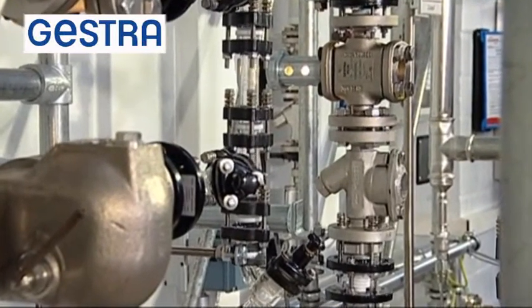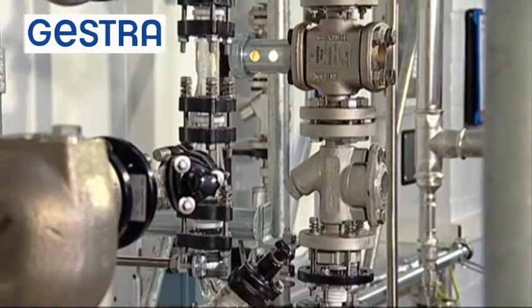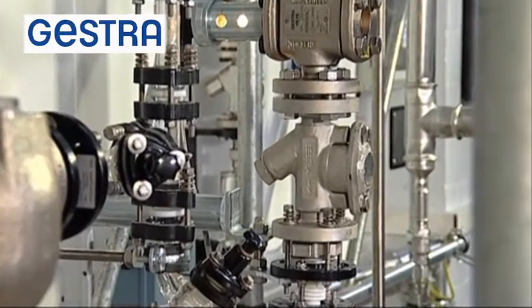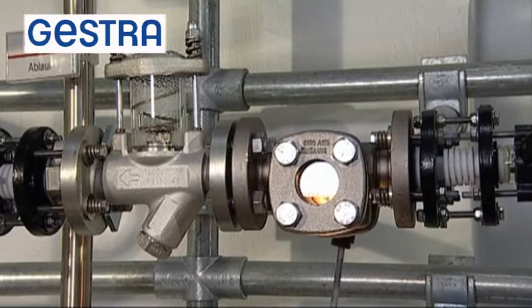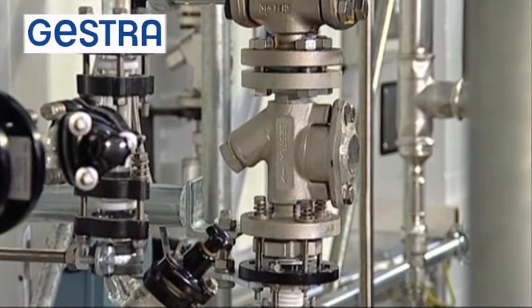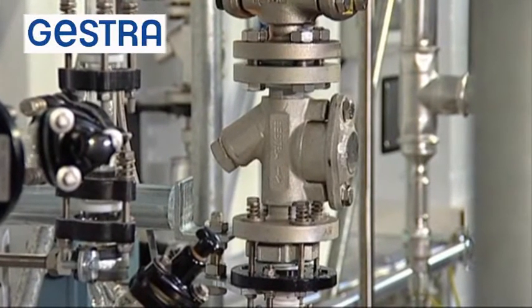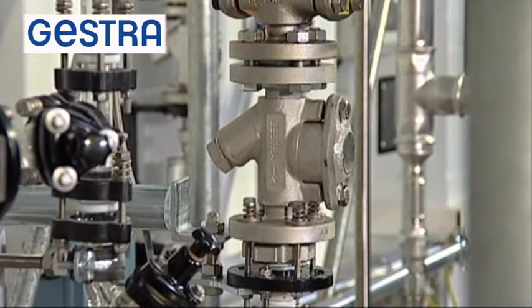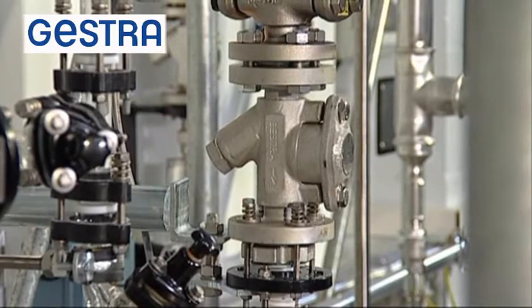This video presents the thermostatic steam trap with membrane regulator, type MK45. Two membrane steam traps are installed here. One is mounted in a horizontal line, the second in the vertical position. With this particular trap, the installation position is freely selectable, horizontal or vertical.